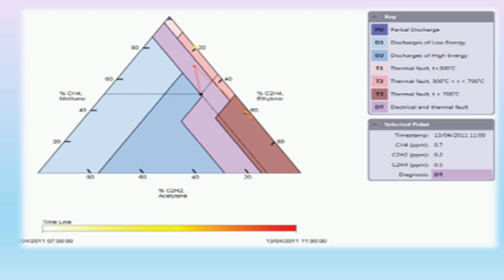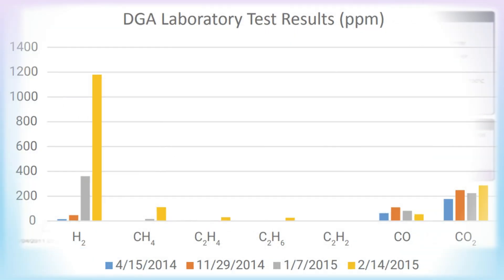As a diagnostic tool, multiple methods of diagnosis have been developed, shown in standards such as IEEE C57.104 and IEC60599, which allow users to relate measured gas-in-oil concentrations to potential ongoing or developing faults. Duval's triangle is based upon the relative percentage concentrations of methane, ethylene and acetylene plotted on a triangular coordinate system. It is a useful technique which produces a diagnosis regardless of gas concentration and has a proven low percentage of error.